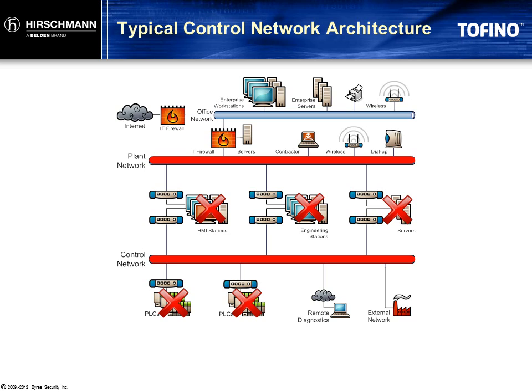It may take only minutes until the entire plant goes down. In addition, it's very likely that we could infect other facilities, since our control network includes connections to an equipment vendor for remote diagnostics and also to a partner organization with whom we share telemetry information. The firewall was doing its job just fine, but it was helpless to prevent this incident because the source of the threat was already inside the plant.